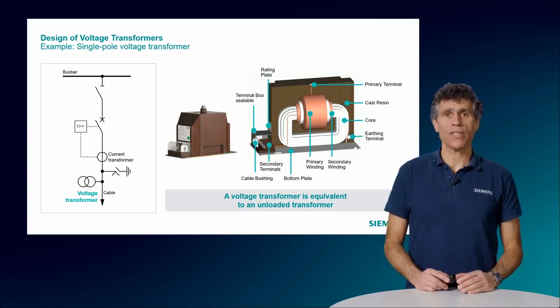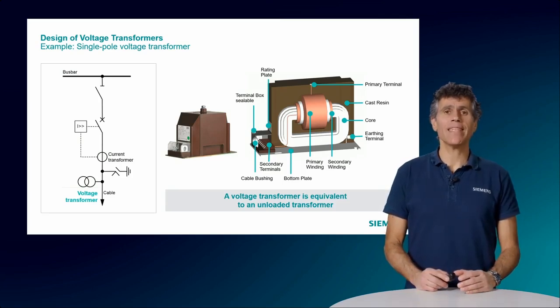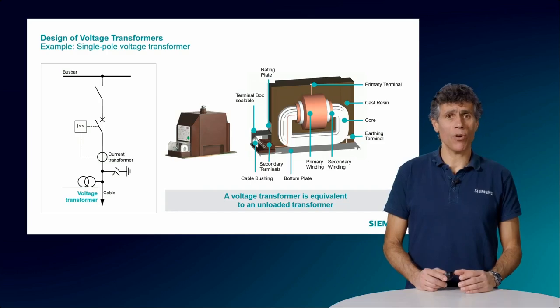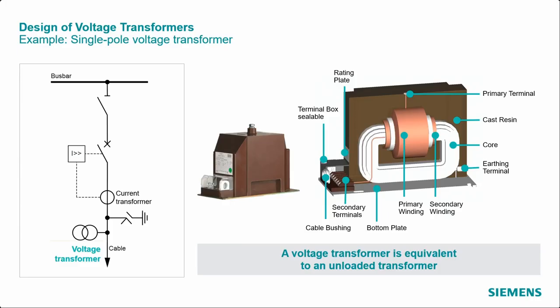For insulation and protection against environmental conditions, the winding and the transformer core are embedded in cast resin, using the same principle as we saw for CTs. This material provides excellent dielectric strength to withstand high voltages, while also protecting the internal components from moisture, dirt, and other contaminants. And finally, the earthing terminal.